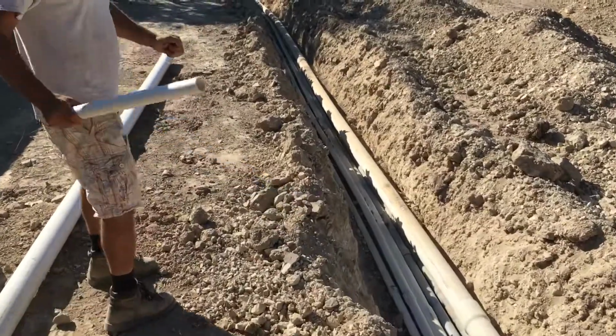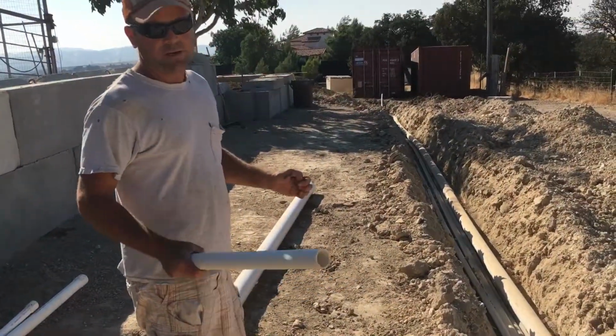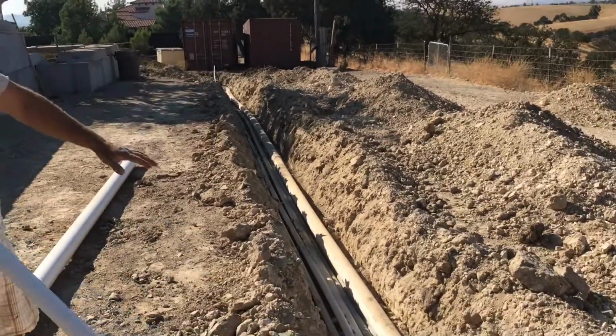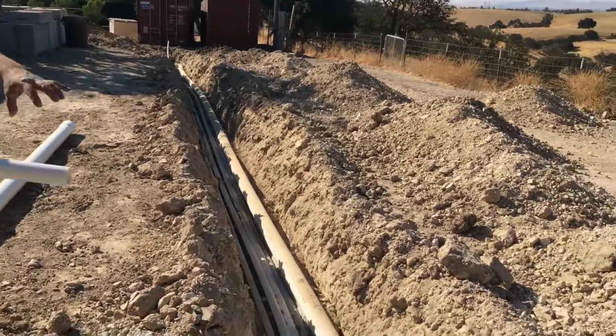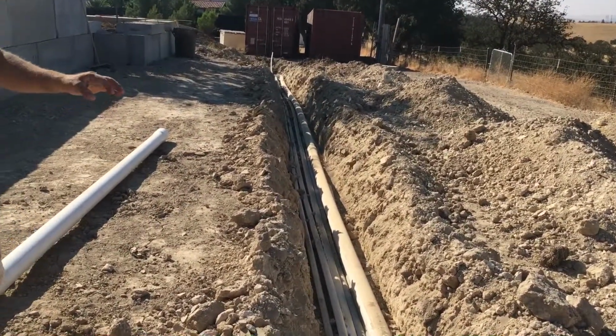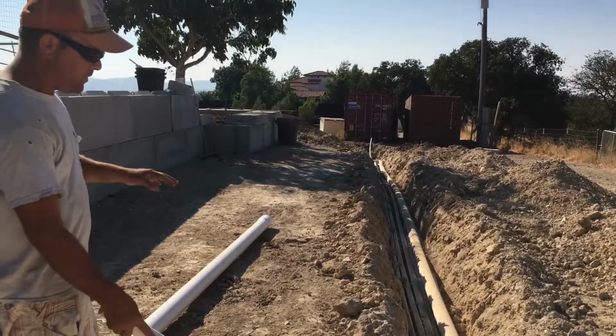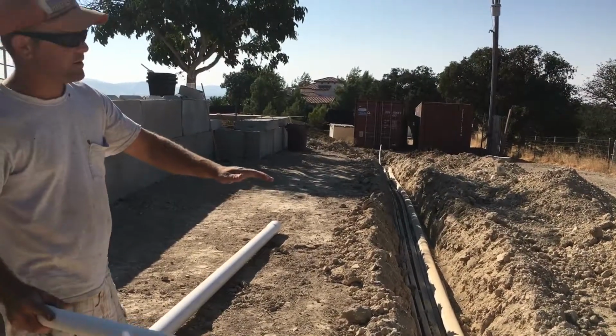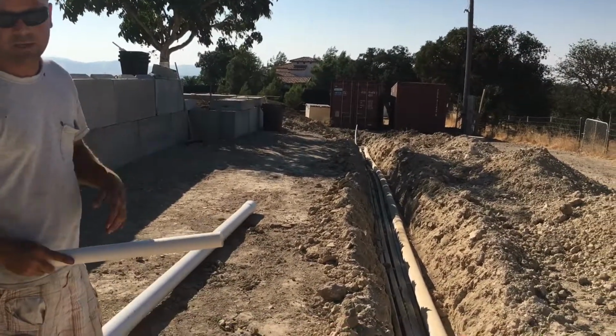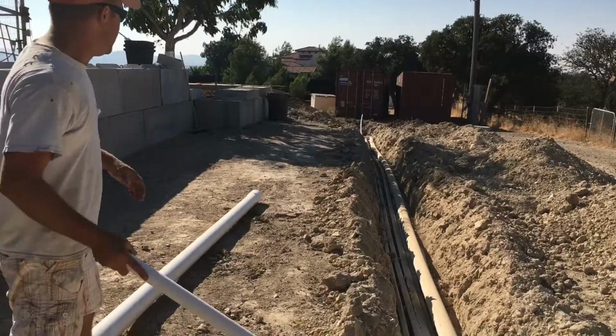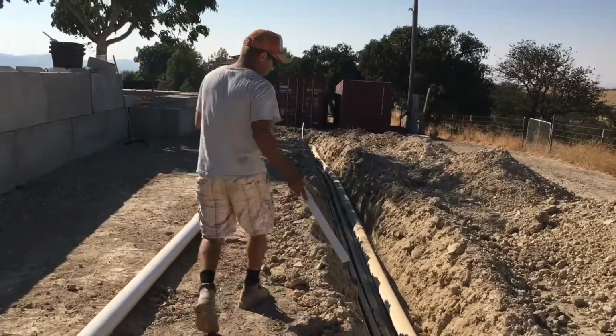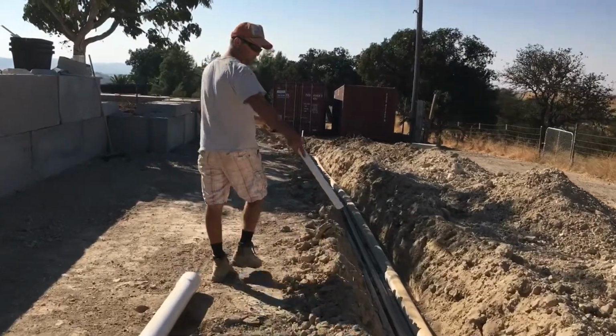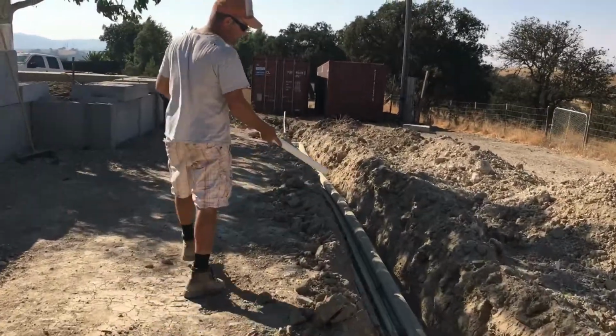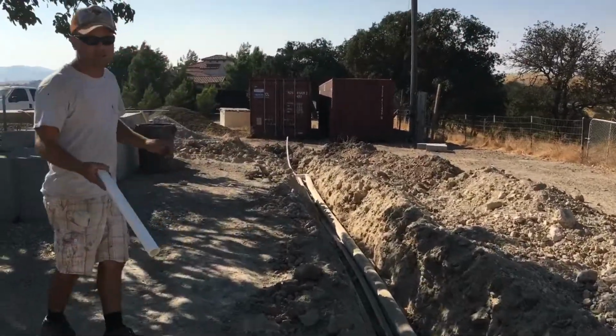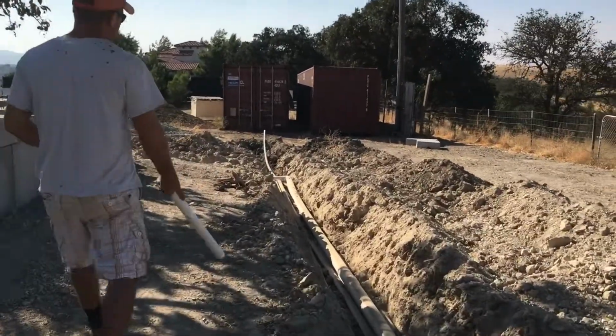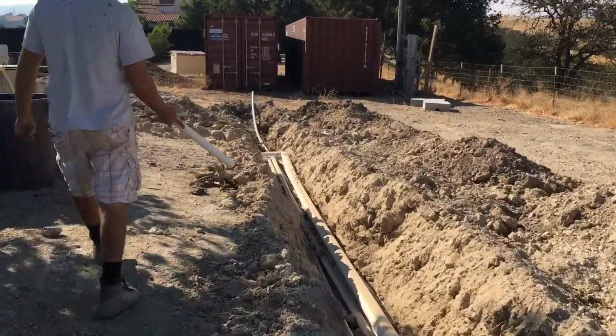I have a load of sand coming Monday or Tuesday so we can backfill this a little better, and I'm going to lift the pipe up a bit so nothing's sitting on top of each other - there'll be a sand buffer between it. The total grade here also has to come up another 6 to 8 inches, so we'll be over a 3-foot depth here. The 4-inch pipe run totaled about 260 feet, so you can imagine, looking at how many pipes we have here, what the total distance is.